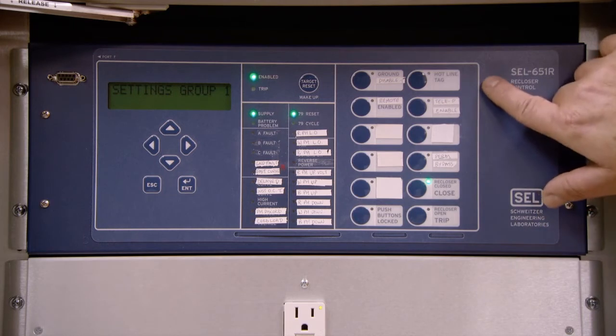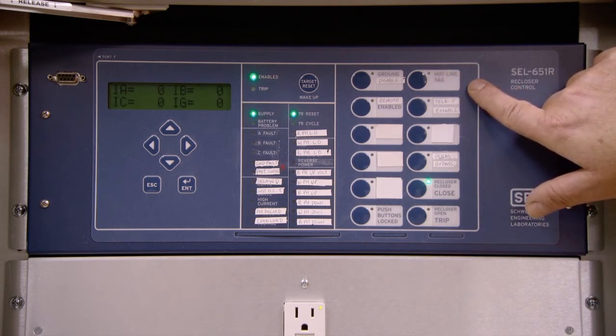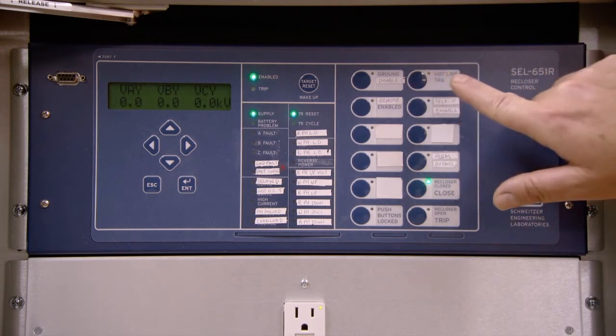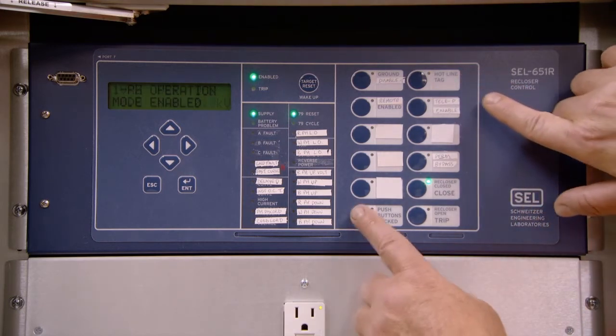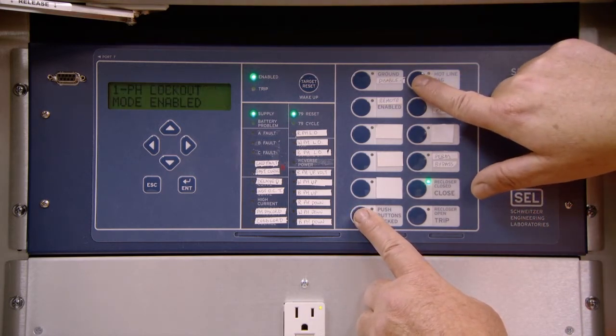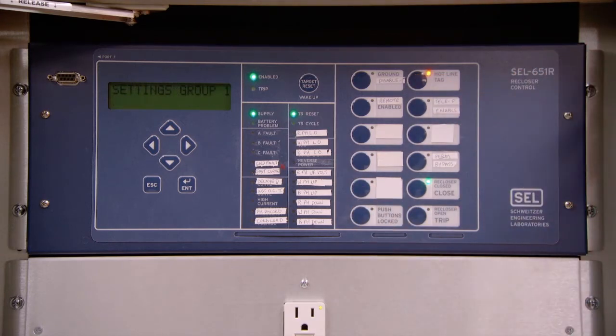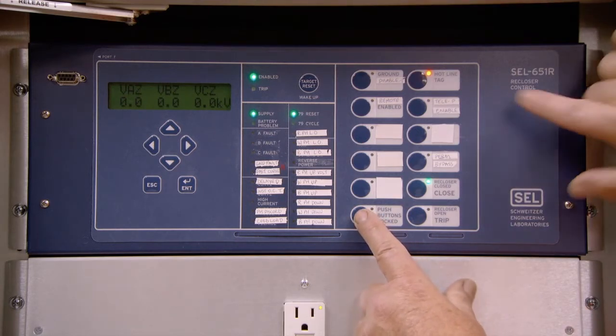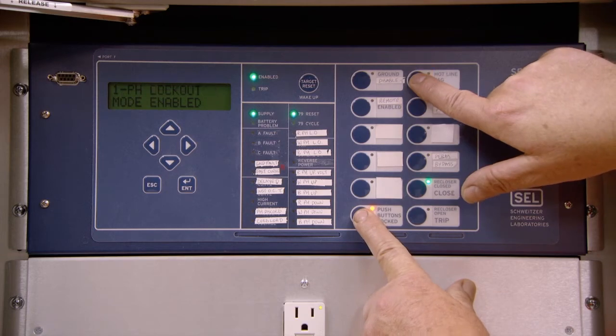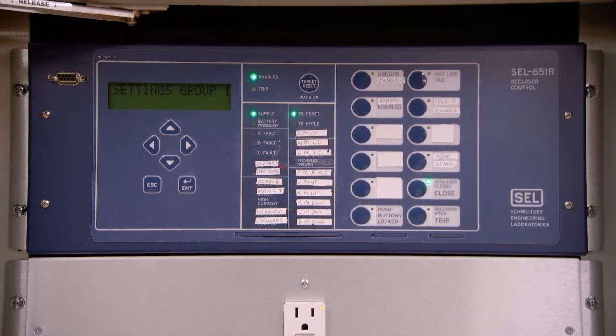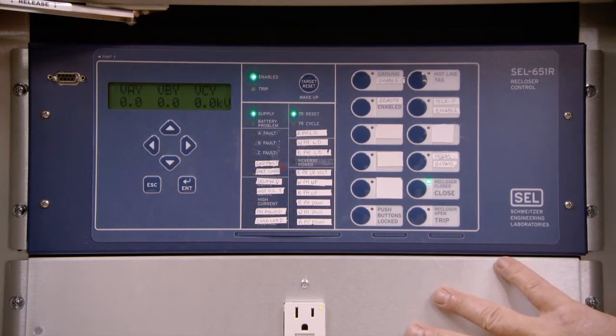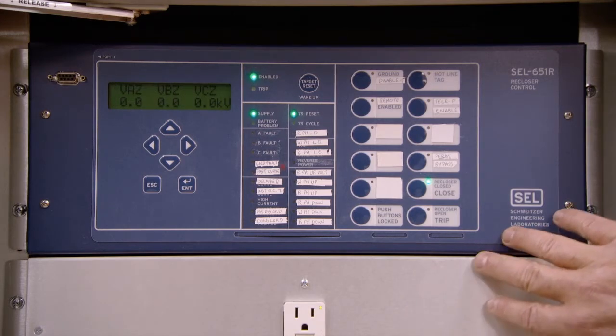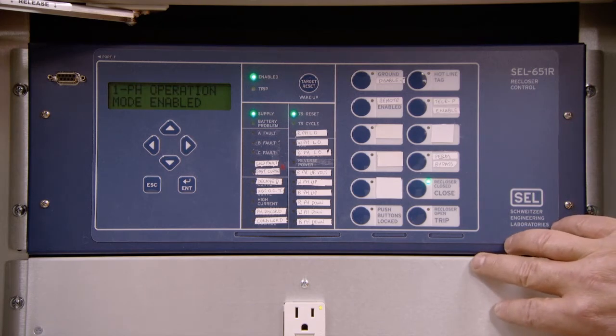For example, if one tries to apply the hotline tag button, nothing will happen unless you use the two-finger operation. First, the push buttons locked button must be applied, and while it is being held down, then press the hotline tag button to achieve the functionality of the desired operation. To remove the operation is the same process. The unit is now set up so that it is an individual trip.